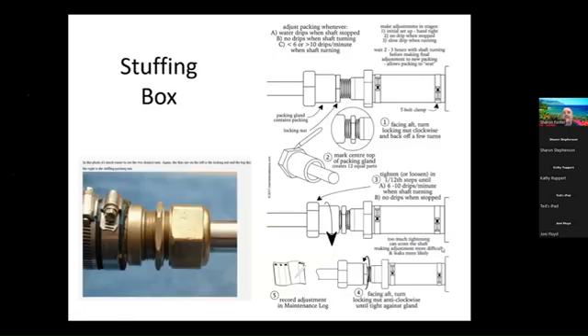All right. Stuffing boxes. This is another thing I get a call quite often on, is adjusting the stuffing box. Most of your standard stuffing box is going to look like the one that's on the screen here. On larger ones, they're going to have a collar with a bolt on each side. That has the packing in it. On this one, the actual packing is in the nut itself.